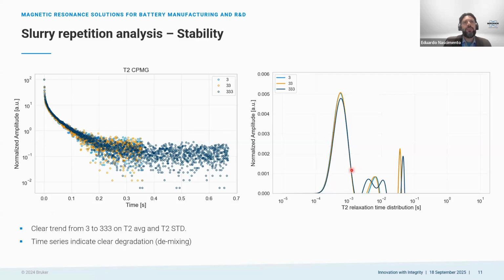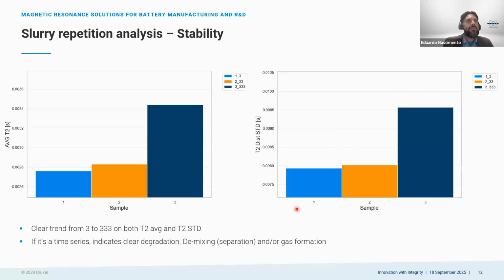So you can see for the very first 2 measurements, for the color blind people, the blue and the orange spectra here are overlapped. But for the last one that was measured at the end of the day, this peak here starts to separate, and even the peak on the right starts to shift to the right. And this is a clear indication that something was going on. So another way to analyze the same data is that you can transform that graphic into a number, like calculating the average T2, or even the distribution standard deviation. And again, you can see that for the very first 2 samples, the numbers are quite comparable, but for the last one, the sample was already demixed.